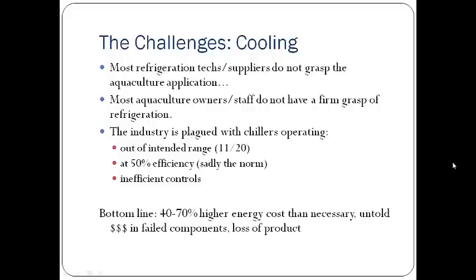It basically amounts to a plague on the industry - for example, chillers operating out of their intended range. One site I visited had 20 chillers that couldn't reach their temperature. After investigation, I found that 11 of them had compressors operating below what the manufacturer recommended.